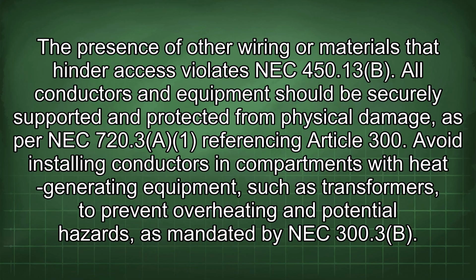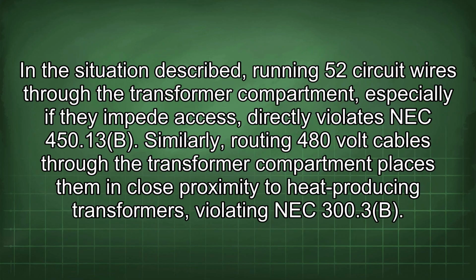mandated by NEC 300.3b. In the situation described, running 52 circuit wires through the transformer compartment, especially if they impede access, directly violates NEC 450.13b. Similarly, routing 480-volt cables through the transformer compartment places them in close proximity to heat-producing transformers, violating NEC 300.3b.